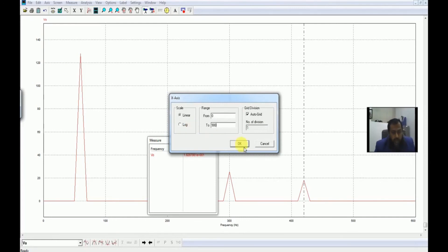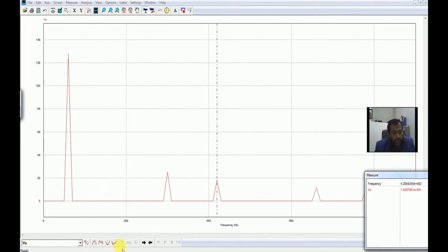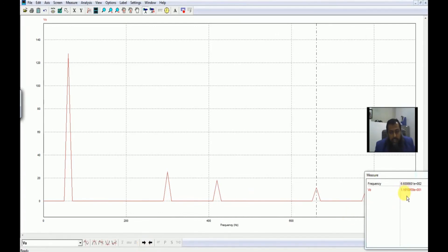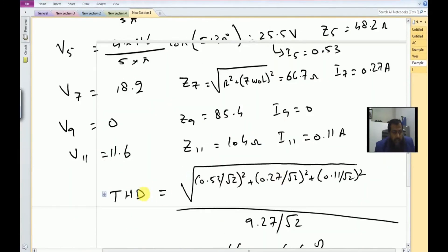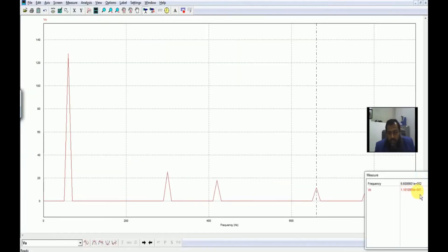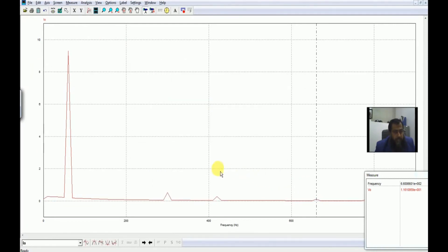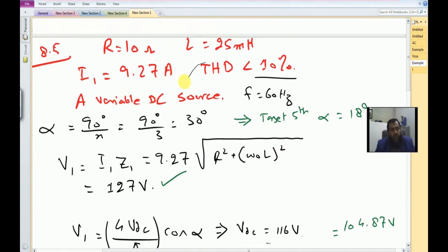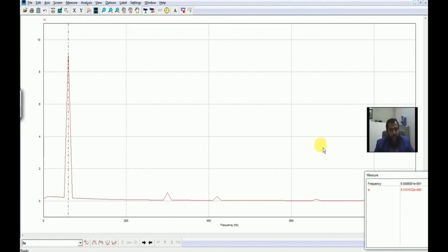Expanding to 900 Hz, we can see all triplen harmonics are absent — no third harmonic and no ninth harmonic. We do have the 11th harmonic at 660 Hz equal to 11.6 volt, which matches exactly what was calculated: 11.6 volt. For the output current I0, the fundamental component is 9.31 ampere, and for this example it was calculated that I1 should be 9.27 ampere. This is how we can get rid of unwanted harmonics without incorporating bulky filters. Thank you very much.